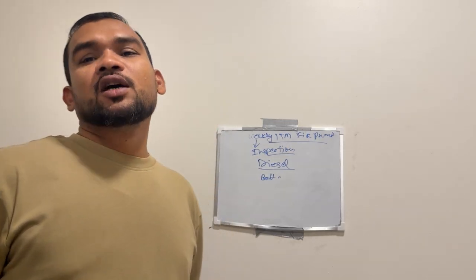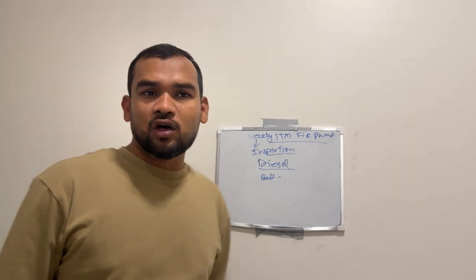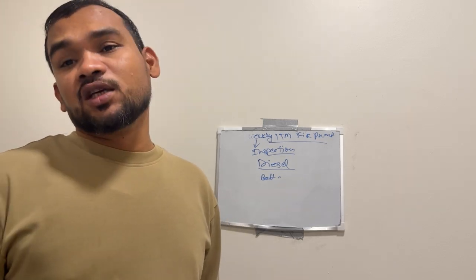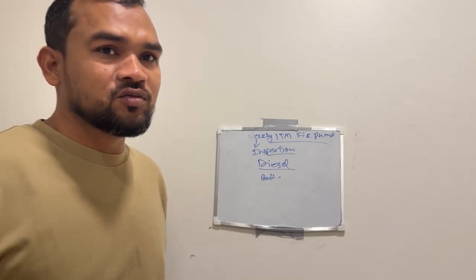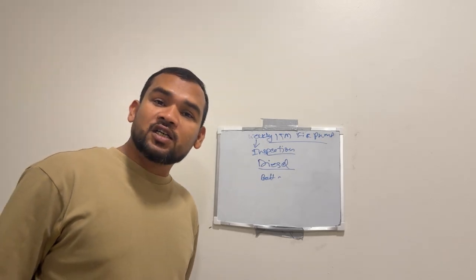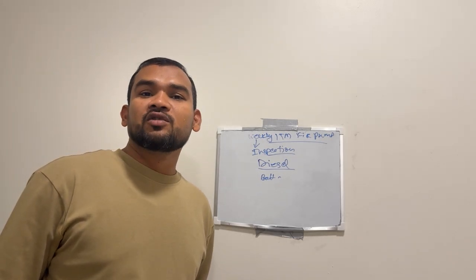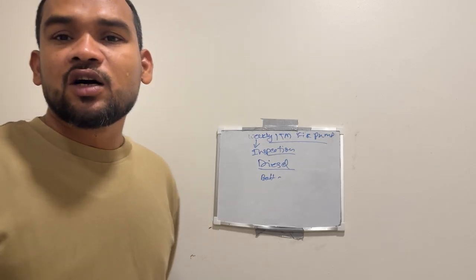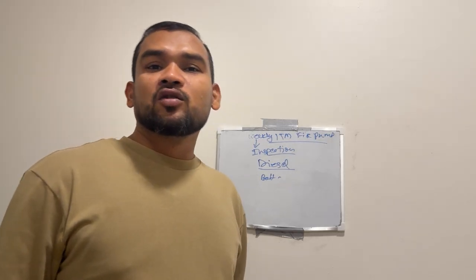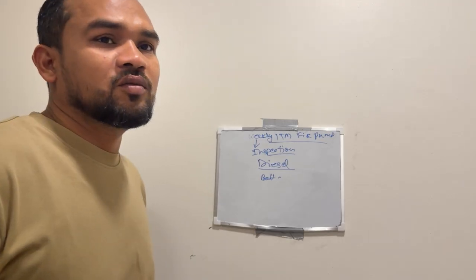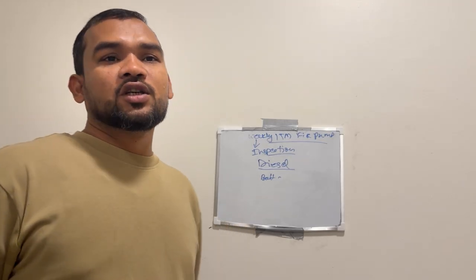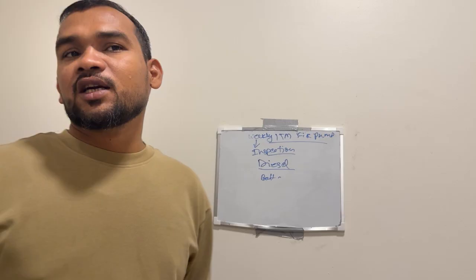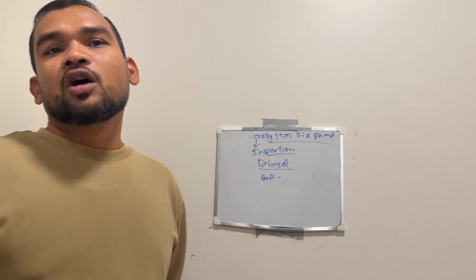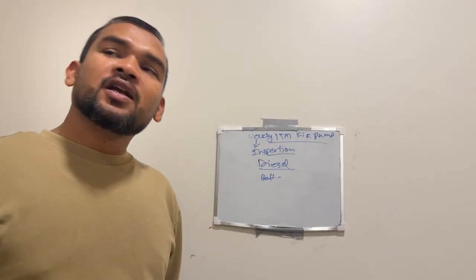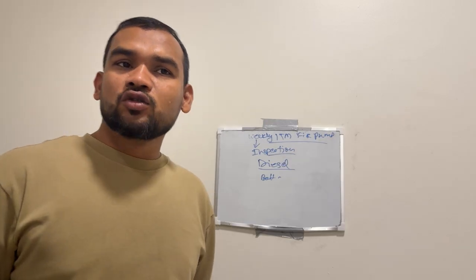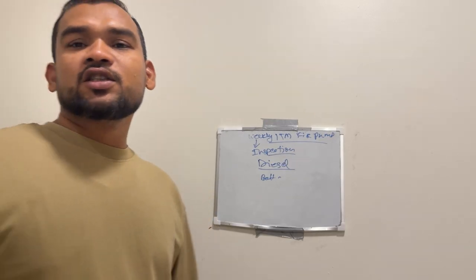So these things we have to check in the diesel engine. Also we have to check the circulation relief valve. If a circulation relief valve is installed in the system, we have to inspect it at the same frequency, weekly. When we do the visual inspection of the pump house and diesel or electric controller, we have to verify the circulation relief valve. The inspection shall confirm that water flows through the valve when the pump operates at shut-off pressure, to prevent overheating. This is topic number 1.